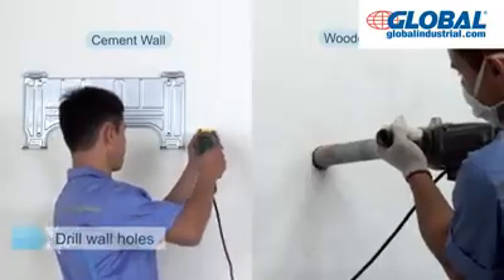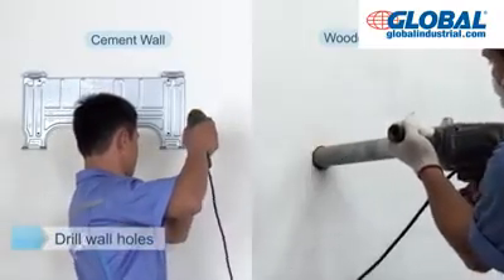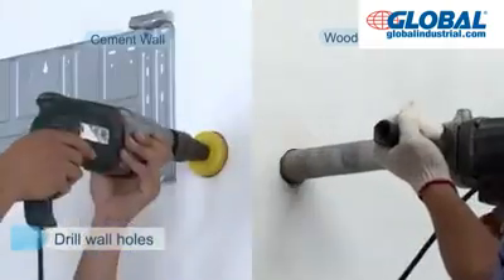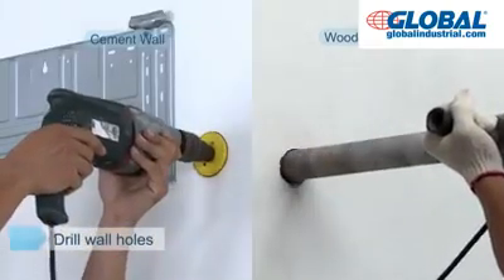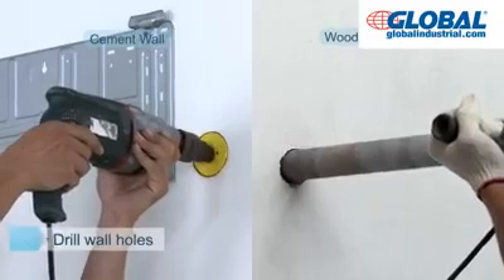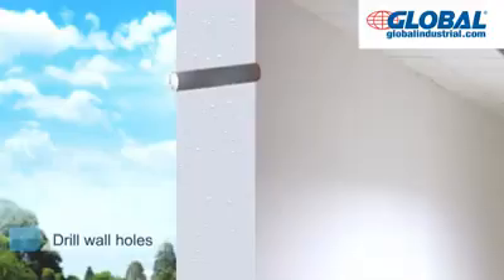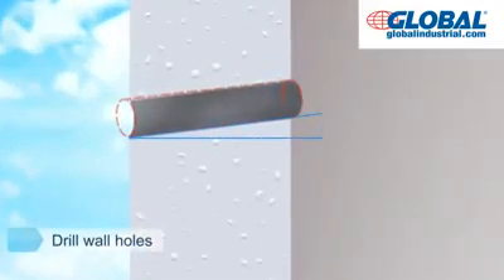Determine the wall hole position according to the exit pipe direction and the expected installation position of the outdoor unit. Avoid wires and other foreign materials. Attention should be paid that the inside of the hole should be about 0.5 inches higher than the outside. Put on the wall socket.